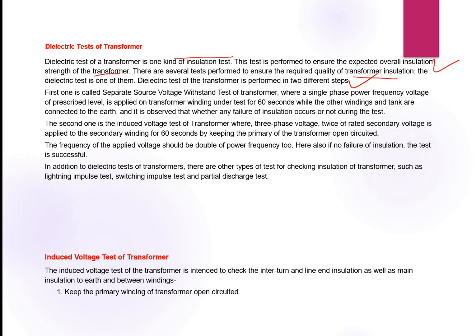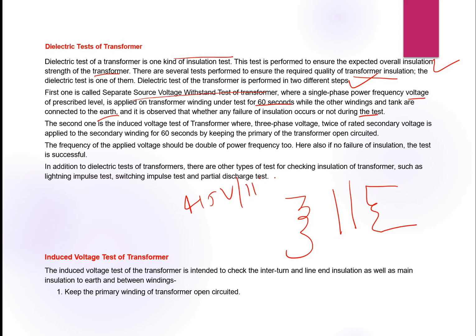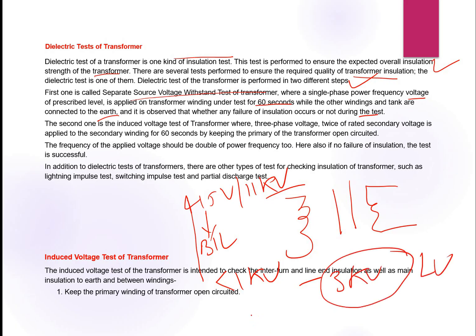First one is called a separate source withstand voltage test, a single phase power frequency voltage test, and it is applied on transformer winding for 60 seconds while the other winding and tank are connected to the earth. It is observed whether any failure of insulation occurs or not during the test. This is the core, this is the primary, this is the secondary. If you are measuring a 415 volt by 11 kV transformer, where the BIL level is less than 1 kV, it means 3 kV separate source applied on LV, and if this is the 11 kV, it means 28 kV on HV side. And what is the connection?